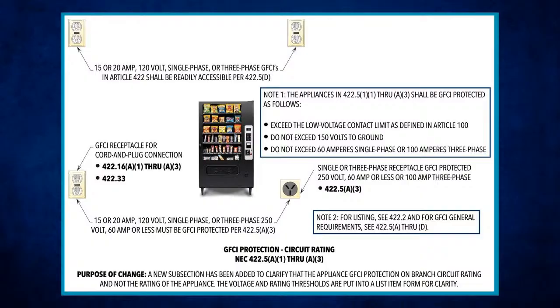So now, if I go back up and look at 422.5a, the last sentence in that first paragraph says multiple Class A protected devices shall be permitted, but shall not be required. So now if I go back down to 422.5b and pick up my typing location, if I have it factory installed within the appliance, then I don't need it upstream. Sure, and that is why the Standards Council reversed 625.54B.